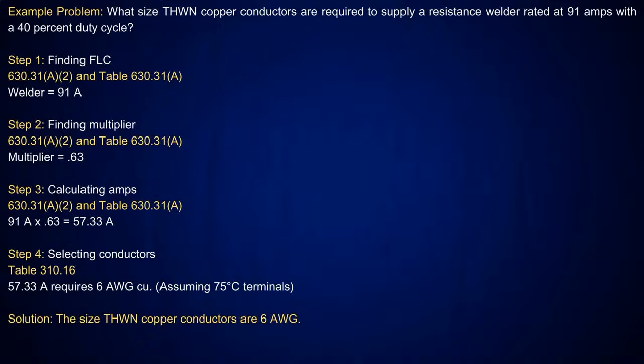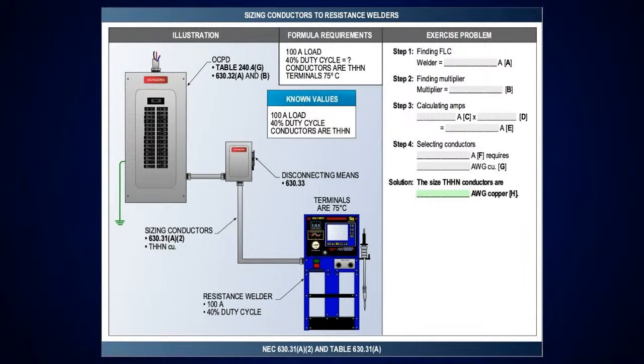Here's a resistance welder. Remember I said when we get there, you want to look at table 630.31(A). We got a 91 amp welder with a 40% duty cycle. Same calculation: 91 amps for a welder. Look at table 630.31(A) for 40% duty cycle, come across, and it tells you that multiplier is 0.63. Multiply that by 91 amps, that gives me 57.33 amps. Then step 4, go to table 310.16, pick up the 75-degree C column. The next size above that is 65 amps, which requires a number 6 conductor. Pretty simple. And here's my resistance welder we have.